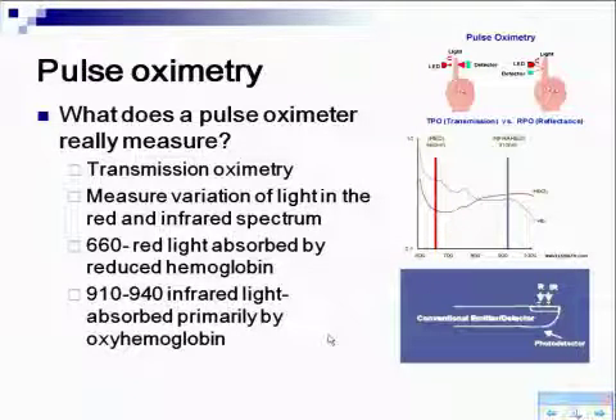The way it does it is by using a diode. A diode is basically a dual emitting device that puts out two wavelengths of light, at 660 and 910 to 940, depending on who you read. At 660, light is absorbed by reduced hemoglobin, and the 910 to 940 range is absorbed primarily by oxyhemoglobin. It then generates a kind of waveform, and from a computer algorithm inside the machine, it is able to determine what the saturation is.